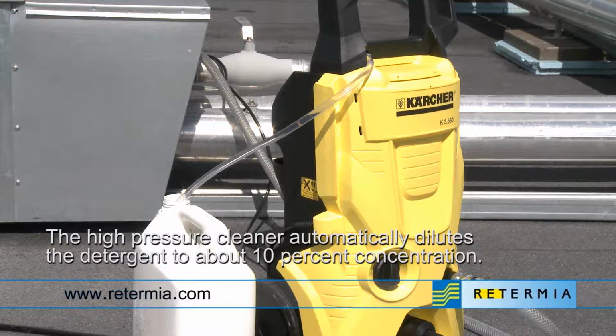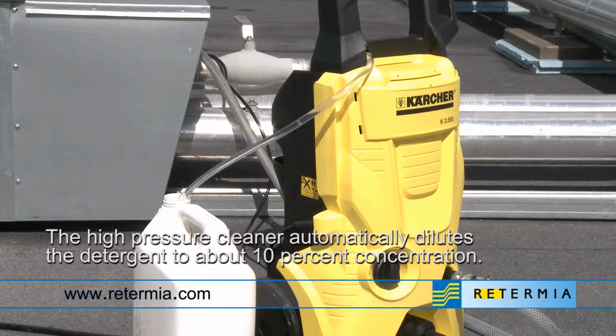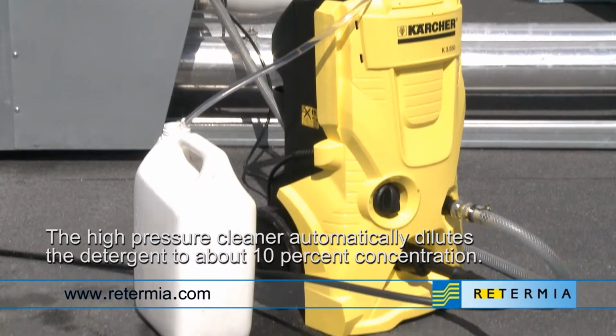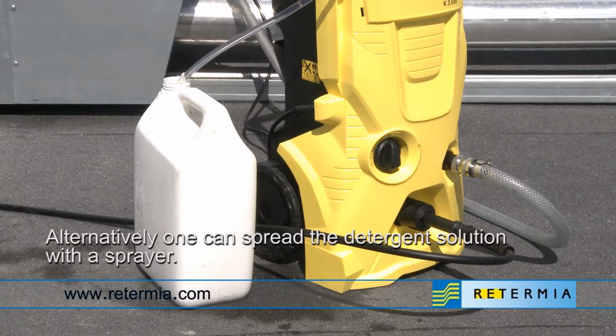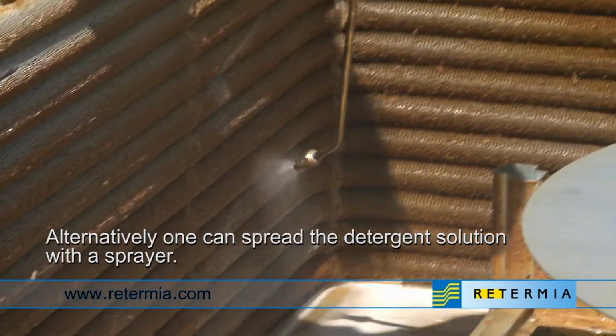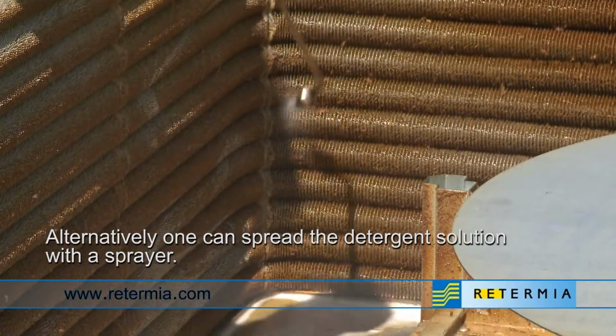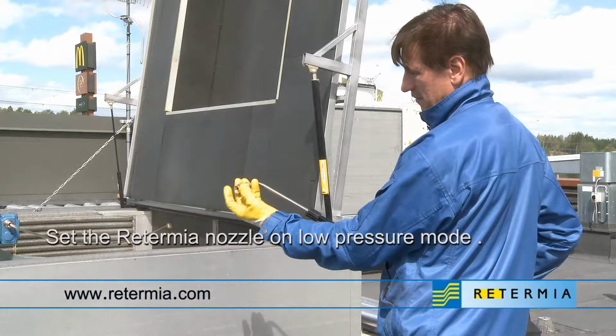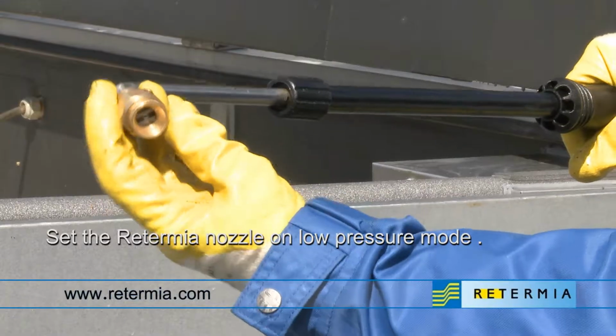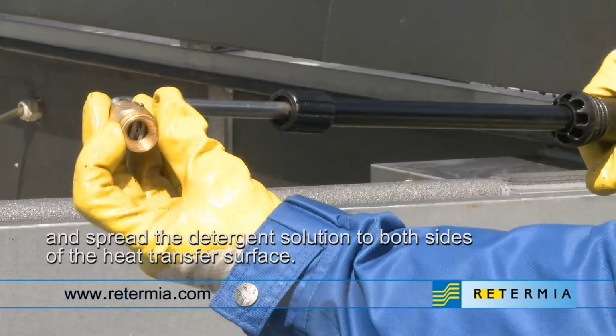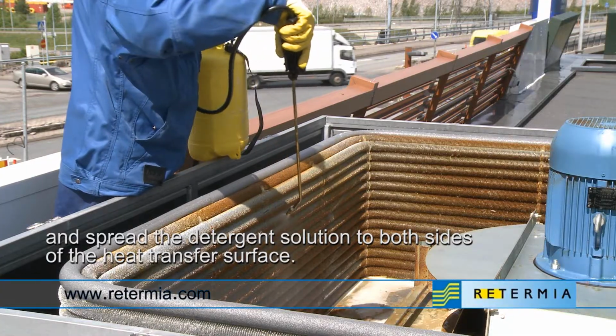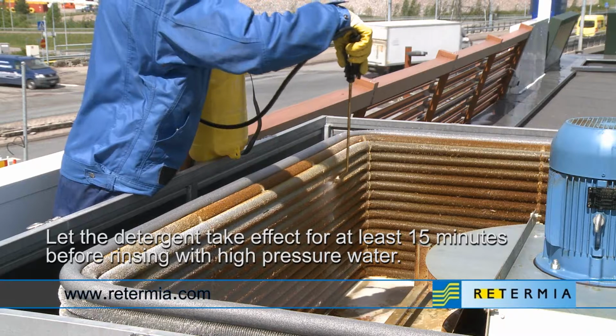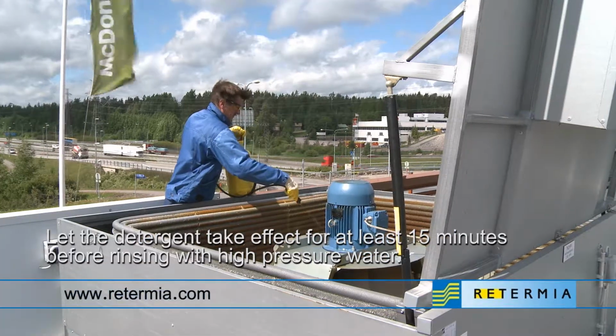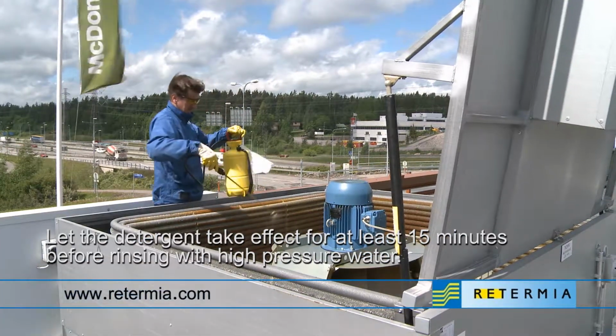The high-pressure cleaner automatically dilutes the detergent to about 10% concentration. Alternatively, one can spread the detergent solution with a sprayer. Set the RETERMIA nozzle on low pressure mode and spread the detergent solution to both sides of the heat transfer surface. Let the detergent take effect for at least 15 minutes before rinsing with high-pressure water.